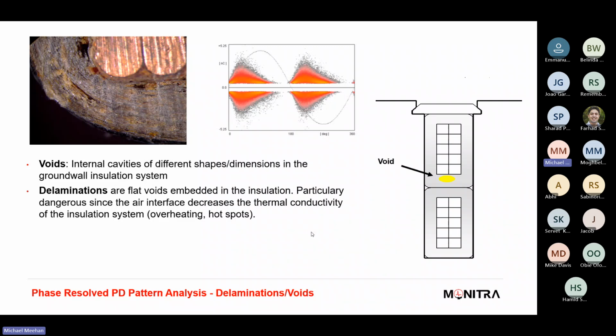And with the way that we do that, we can start to look at not just patterns, but changes in patterns in a more definitive and finite way, by having that sensitivity of machine learning and computerization being that bit more accurate than the human. But if we drill into what a typical void looks like, potentially here we've got a typical PD pattern where we have a phase resolved pattern. It's important to reference the phase resolved pattern here, because for any PD test you really need to have that phase resolved pattern to be able to differentiate noise from PD.